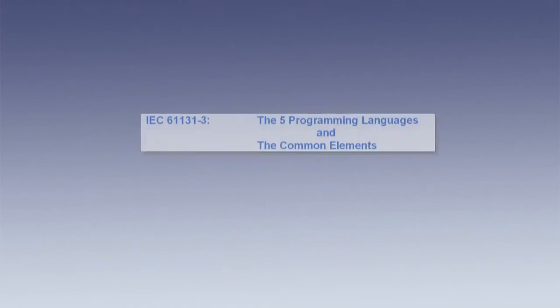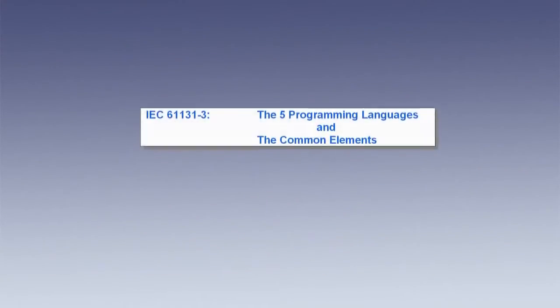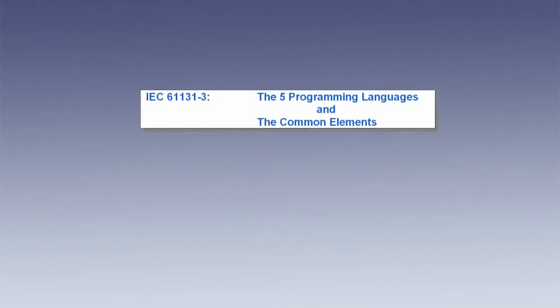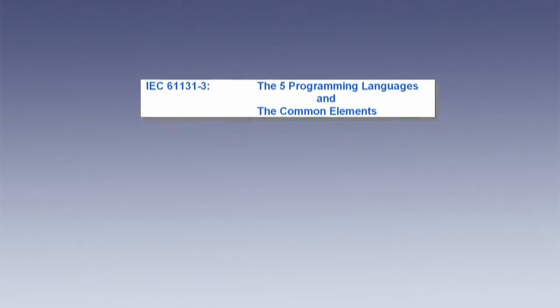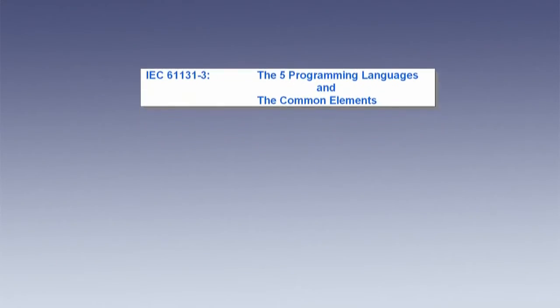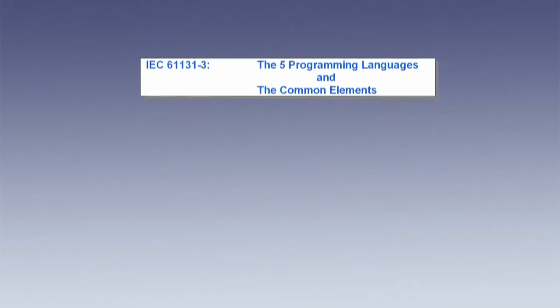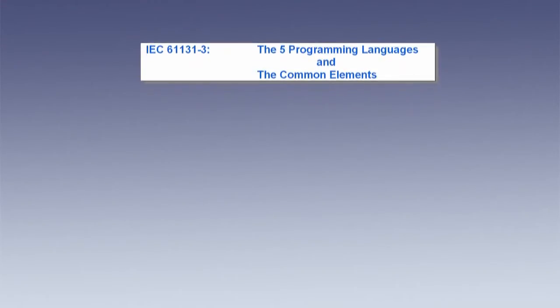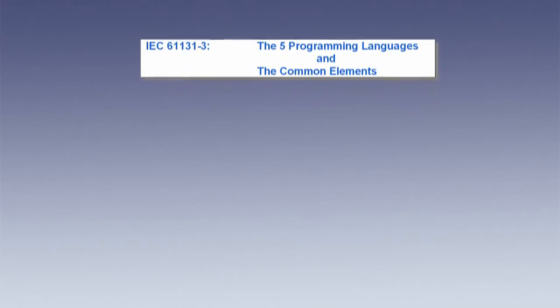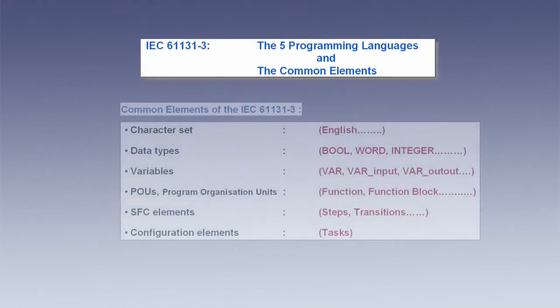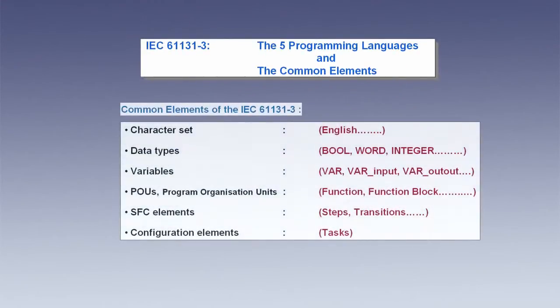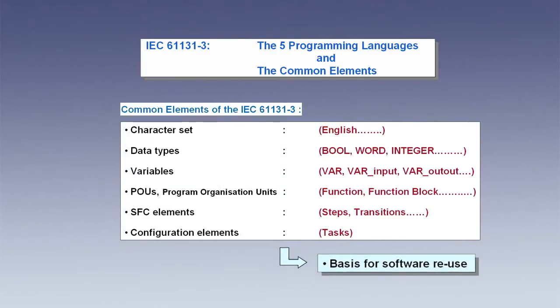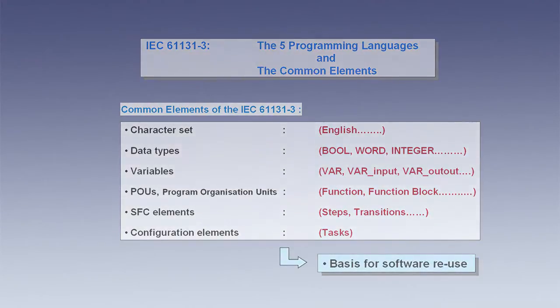The two main parts of the international standard IEC 61131 are the common elements and five programming languages. The common elements, such as data types, variables and program organization units, serve as the basis for reuse within PLC software. Without them, it would not be possible to program functions or function blocks.